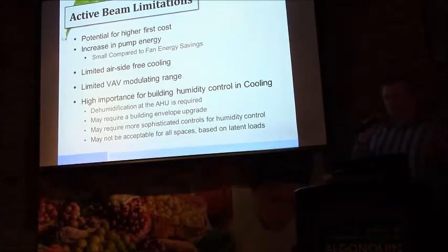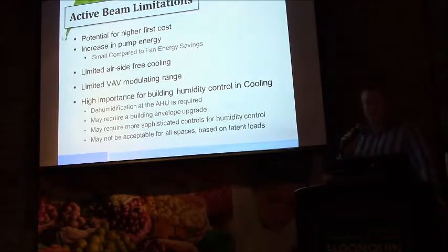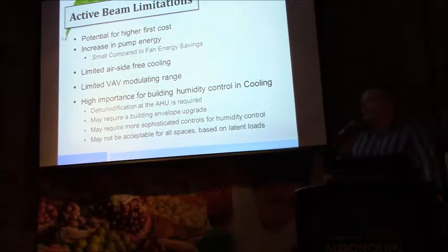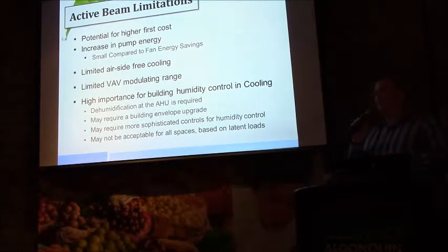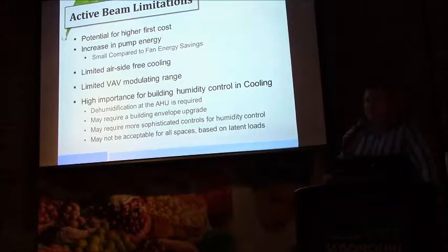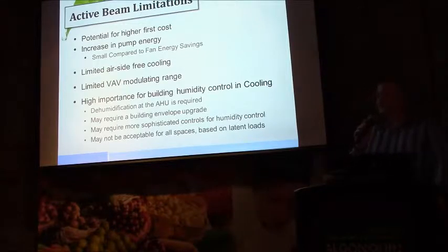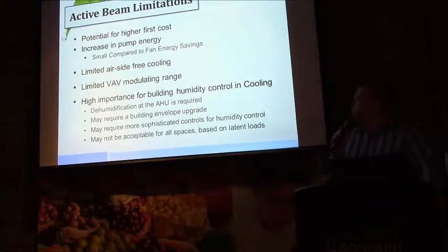But we do have limited airside free cooling, that's a given, and we deal with that on the waterside. We do have limited VAV modulation range, although VAV in terms of being used as a terminal occupancy control device is a great solution and helps us address the risk of overcooling a space that's unoccupied for which the primary air is representative of a high portion of the total sensible cooling.